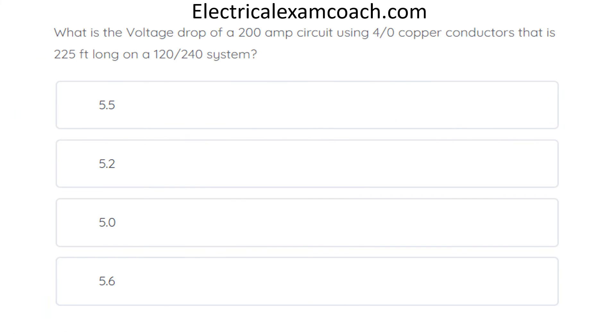What is the voltage drop of a 200-amp circuit using 4-aught copper conductors that is 225 feet long on a 120/240-volt system? The correct answer is 5.5 volts.